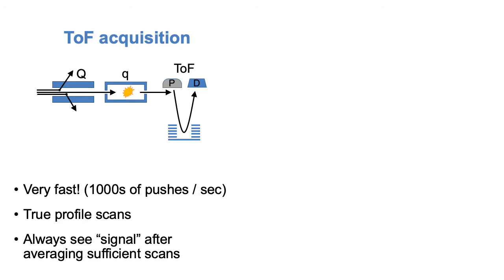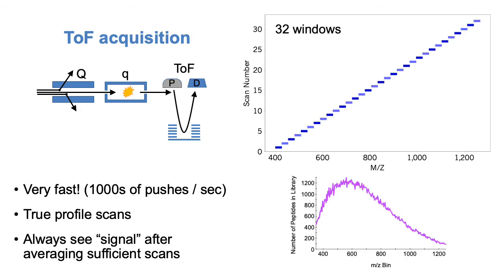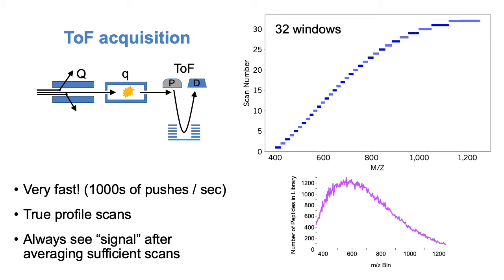Modern DIA methods were originally developed and trademarked as SWATH on time-of-flight instruments. They took advantage of TOF features such as very fast scan rates, and after noticing that peptides tended to clump between 400 and 900 m/z, these 32 fixed window DIA measurements quickly became variable width DIA, where windows were narrower in the sweet spot and commensurately wider at higher or lower m/z.